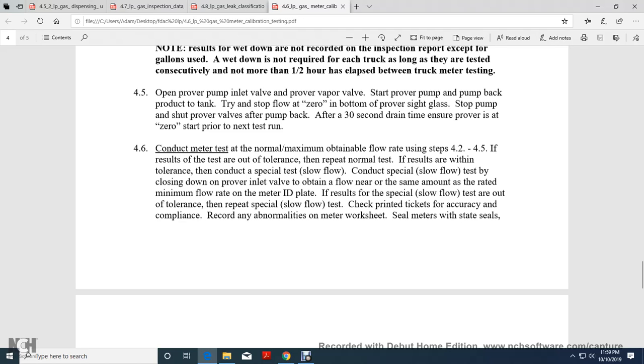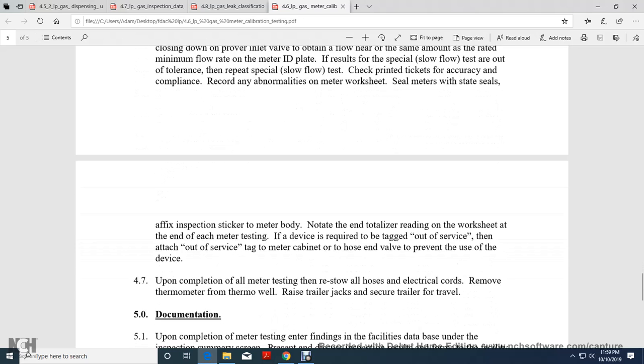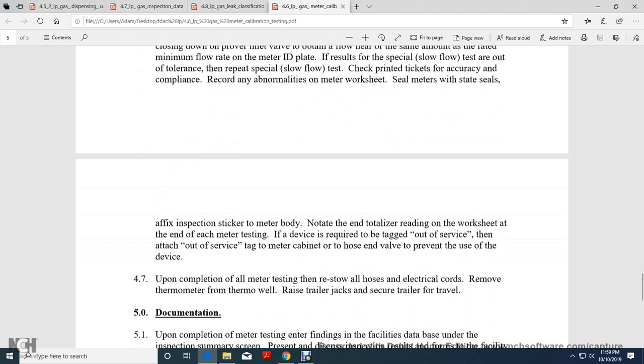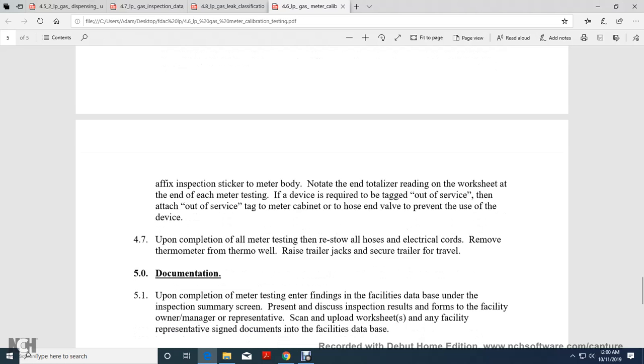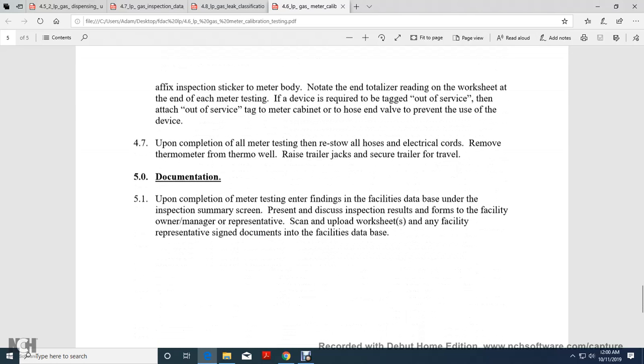Record abnormalities on the meter worksheet. Seal the meter with state seals and place the inspection sticker on the meter body. Note the end totalizer reading on the worksheet at the end of each meter test. If the device is required to be tagged out of service, attach the out of service tag to the meter cabinet. or to the hose end valve to prevent the use of the device.